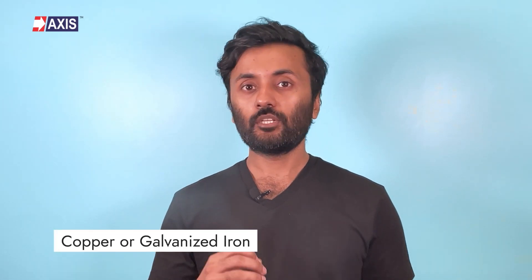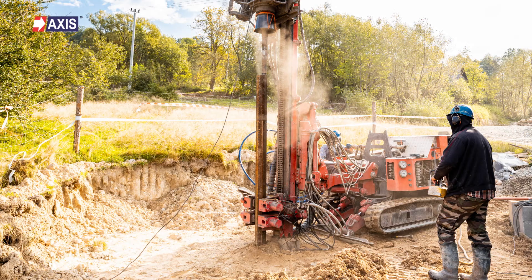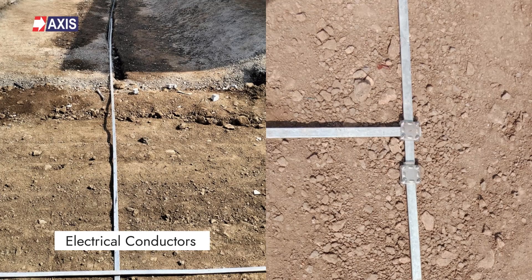Now let's discuss some of the methods we can use for earthing. Firstly, plate earthing. In this method, we use a plate made of either galvanized iron or copper. This plate is buried vertically deep into the ground, usually at least 3 meters or about 10 feet deep. Their dimensions vary based on the fault current rating. These plates are then connected to all your electrical conductors, creating a safe path for any electrical discharge to flow into the ground.